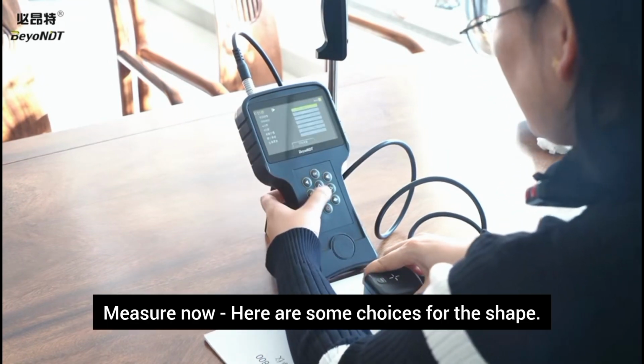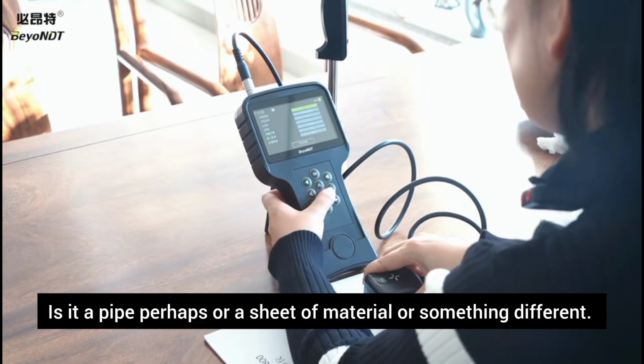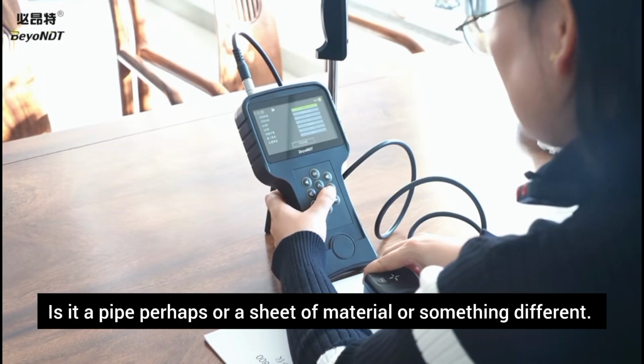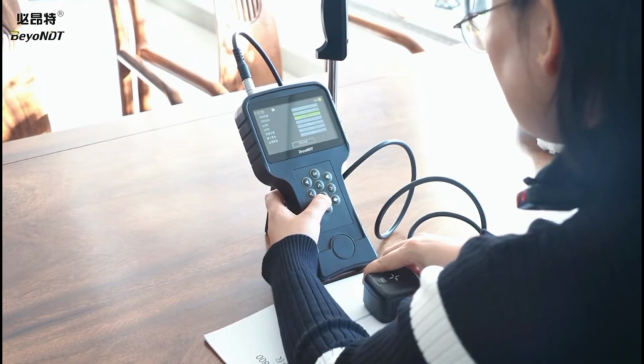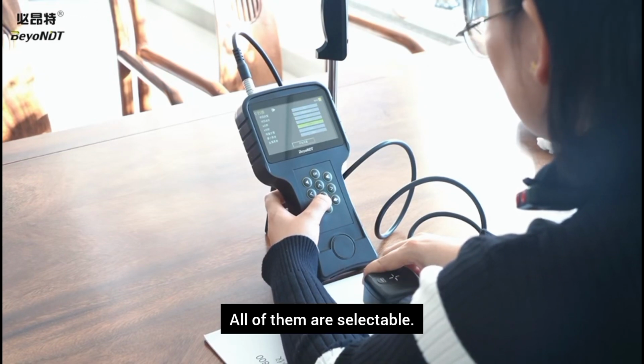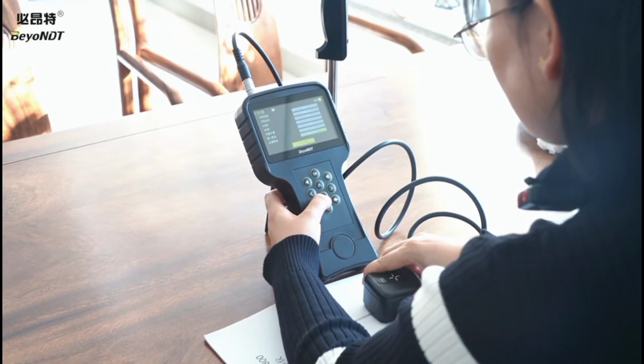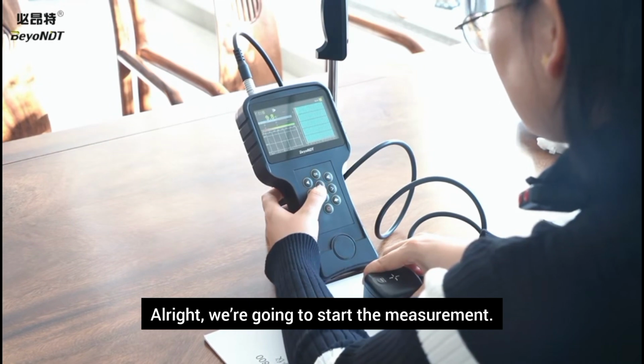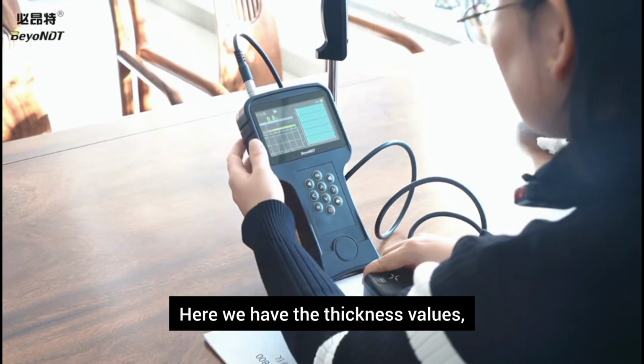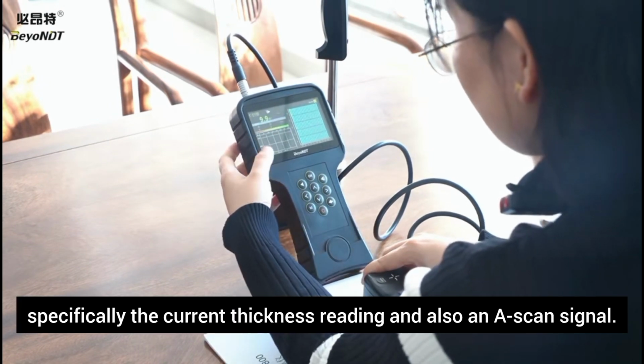Measure now. Here are some choices for the shape. Is it a pipe, perhaps, or a sheet of material, or something different? Please make your selection. All of them are selectable. All right, we're going to start the measurement. Here we have the thickness values, specifically the current thickness reading, and also an A-scan signal. Over here we see a C-scan grid.